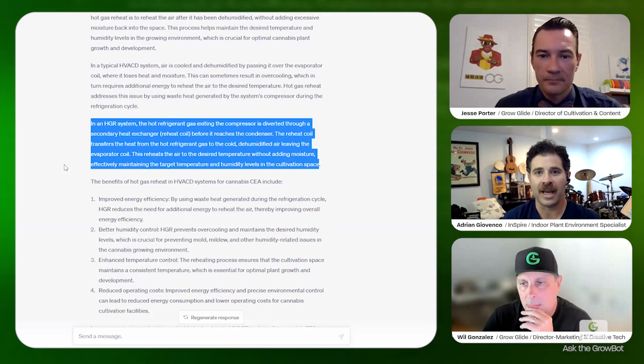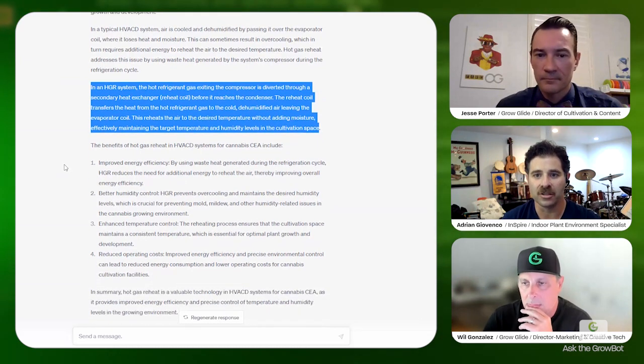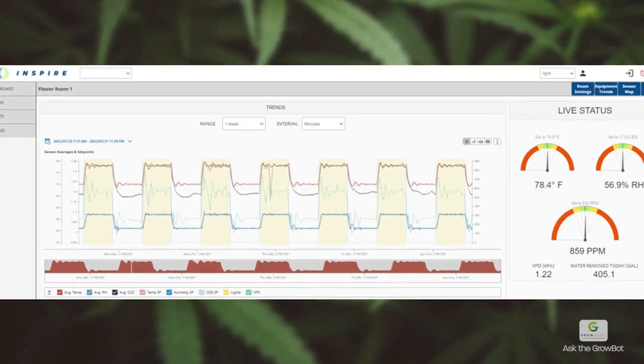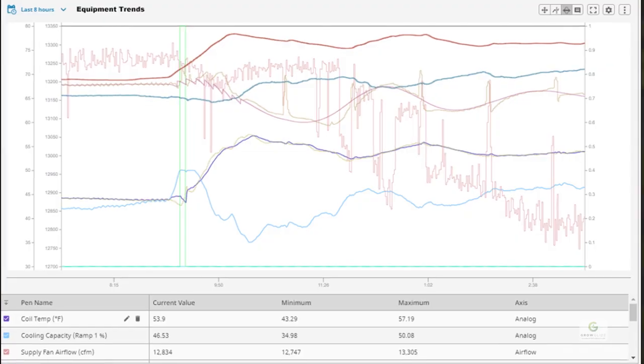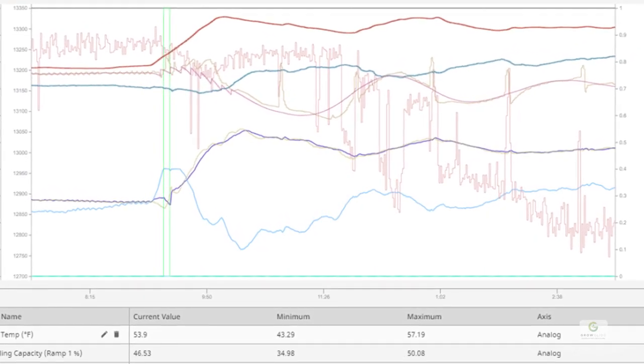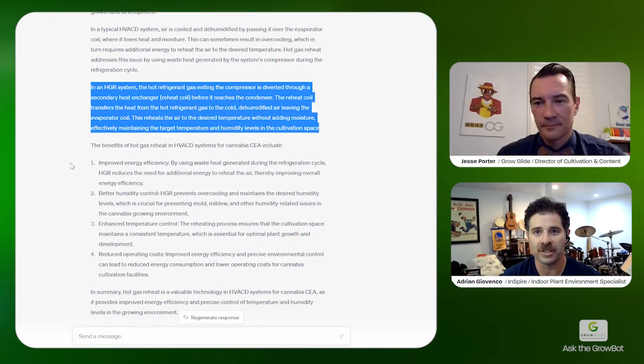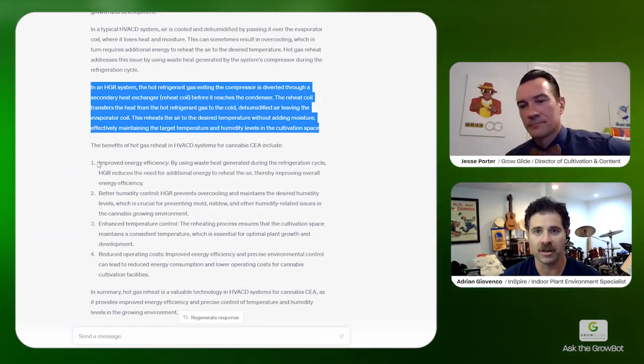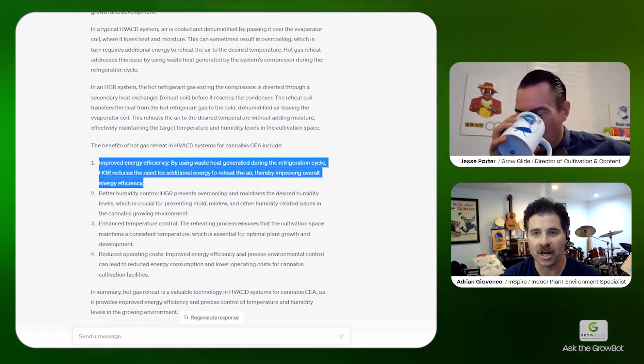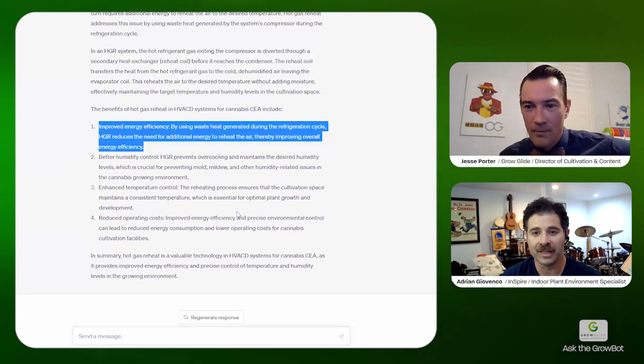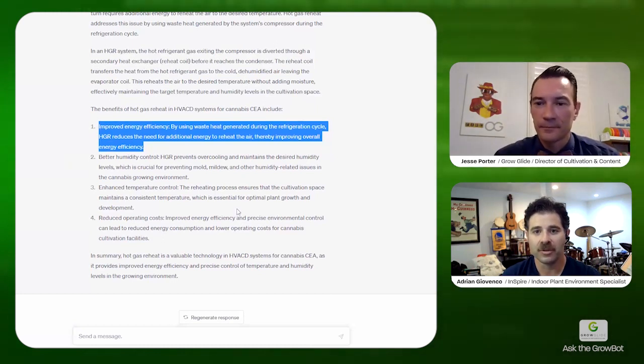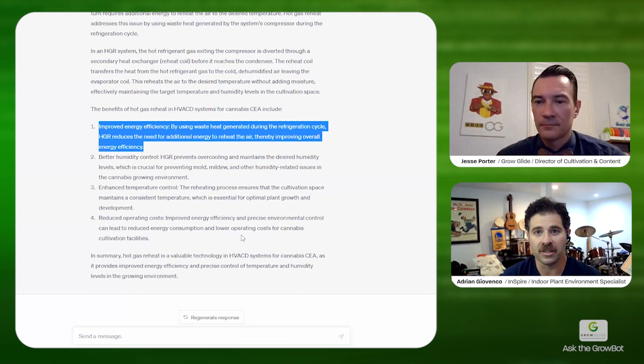And that's really the biggest caveat, I think, that needs to be understood in the space: it's a very dynamic load profile that we handle within these spaces, right? You have lights on and a large dehumidification load is really the predominant load in the space when the lights are on. You also have some sensible load to take care of. And then what happens when the lights shut off? You have zero sensible load in the space. You actually have a negative sensible load because of the little bit of residual evaporative cooling that takes place from the plants. And now you still have a dehumidification load in the space during the lights off period.